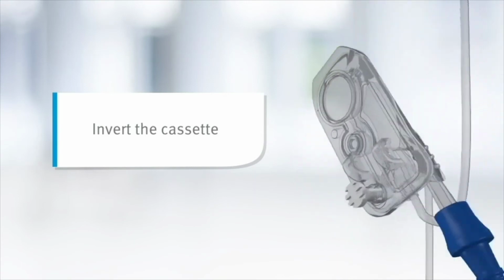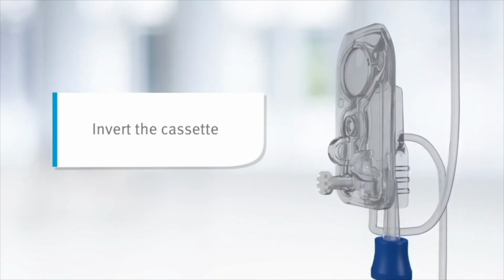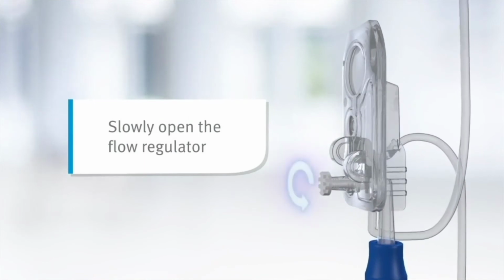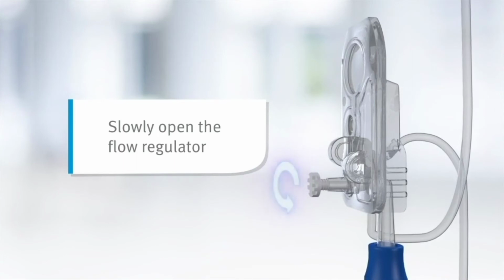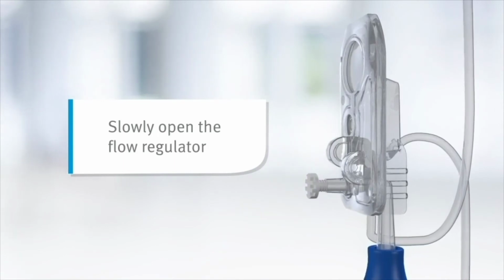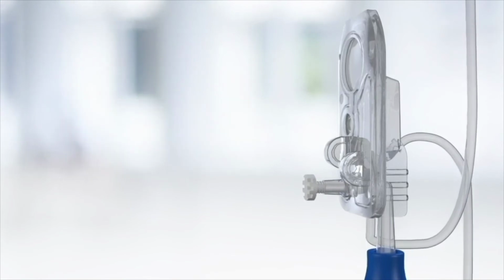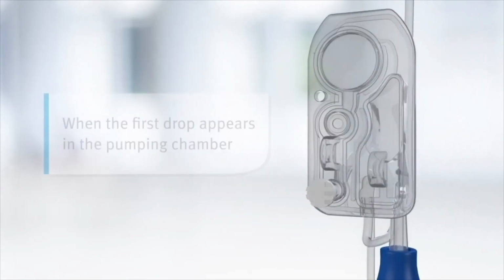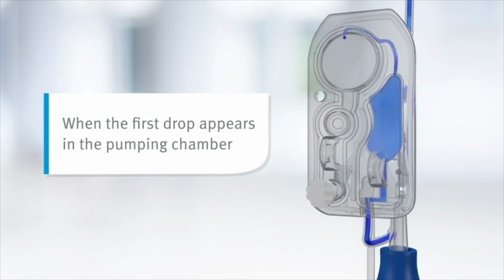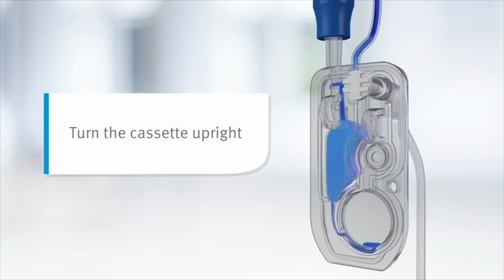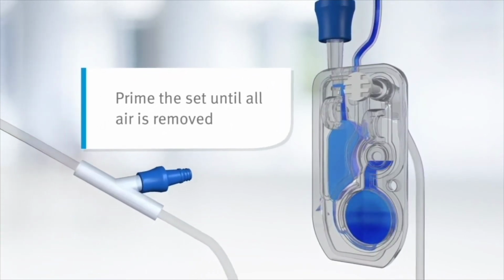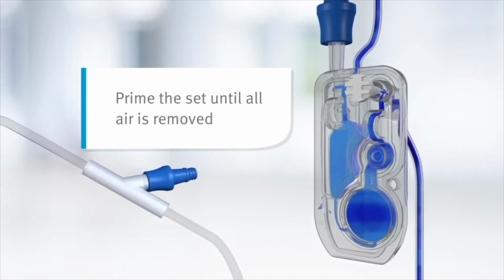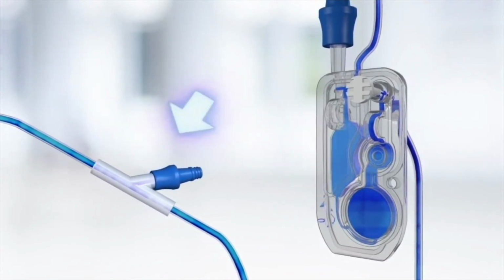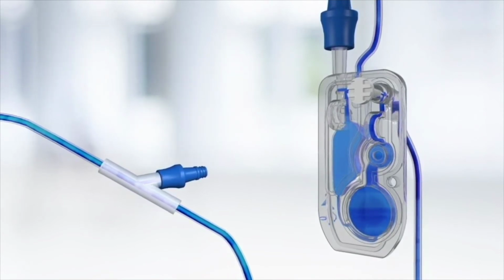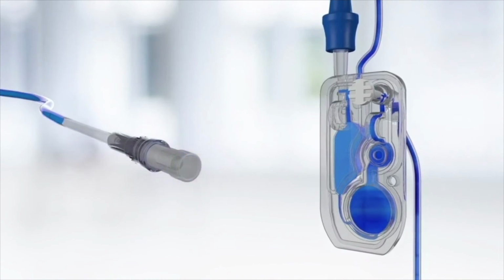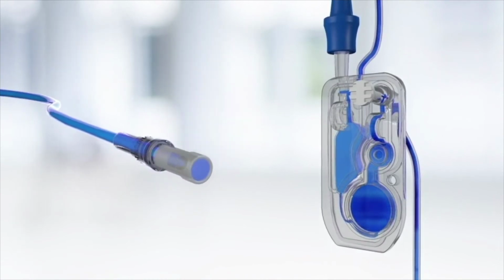Invert the cassette so the secondary port is pointing down. Slowly open the flow regulator by turning it counterclockwise while holding the cassette in the inverted position to allow the fluid to flow into the cassette at a controlled rate. Note, to quickly stop the flow at any time, push in on the flow regulator. When the first drop appears in the pumping chamber, turn the cassette upright. Continue to slowly prime the set until all air is removed from the cassette and the remainder of the tubing. Tap the cassette Y sites and tubing to dislodge air bubbles. Note, if the filter at the distal patient end of the tubing gets wet, you must temporarily remove the cap to continue priming.